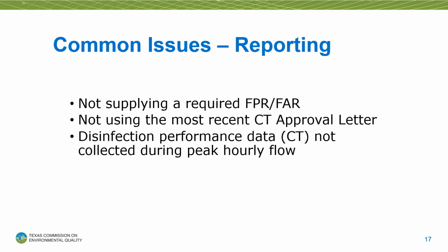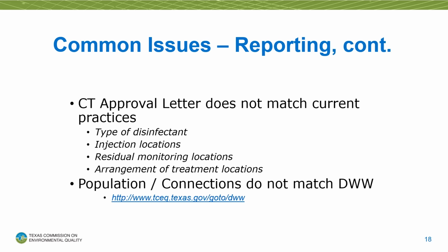Some common issues when reporting could be not supplying a required FPR or FAR, the filter profile report and the filter assessment report. Not doing so could lead to a violation. Not using the most recent CT approval letter, which would cause the compliance calculations to be inaccurate. Another common reporting issue is disinfection performance data not being collected during peak hourly flow. Another common issue when reporting is that the CT approval letter does not match current practices such as type of disinfectant, injection locations, residual monitoring locations, or arrangement of treatment locations. If your system needs to update the CT study, please reach out to the CT study team.